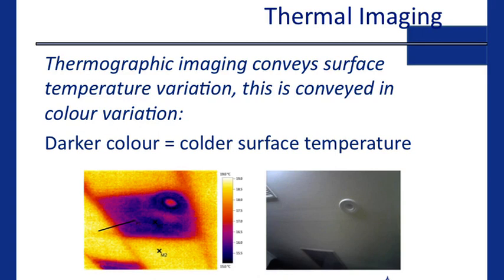For those that haven't seen thermal imaging before, it conveys surface temperature in colour variations. The colder the surface, the darker the colour; the warmer the surface, the more orange or red the colour. Here we have a thermal image and a digital image of a downlight — and what the thermal image is picking up is that the electrician removed the insulation. Very typical of what we're finding. We're still building to the old halogen days where you had to pull the batts away, but we now have better technology where you can insulate up to or over the downlight.